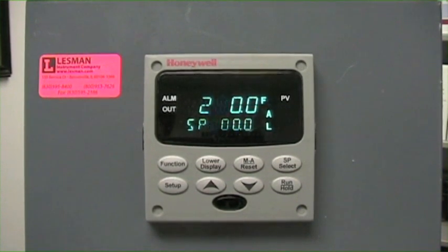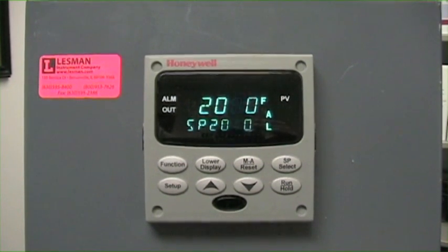Be aware that I have special wiring here in Lesman's process laboratory to fake an Accutune, and to do so without being connected to an actual process. This setup is designed to do a rapid Accutune suitable for a short video. Do not expect your controller to do an Accutune as fast as this laboratory controller, because you'll be tuning on a real process, not on a fake process.